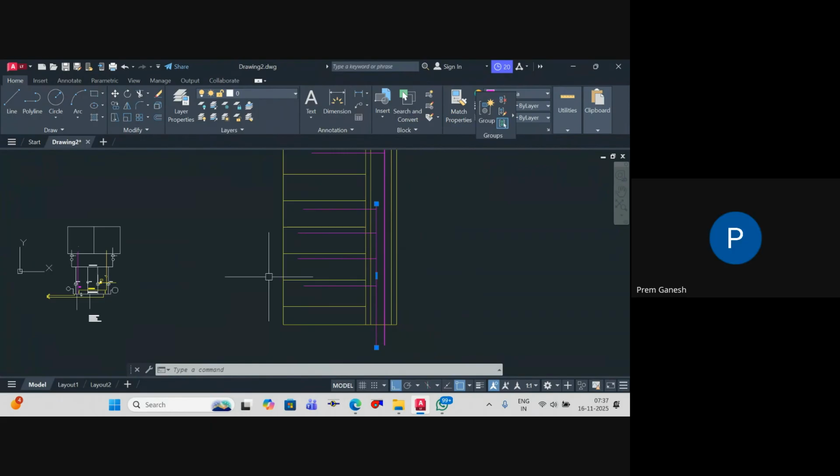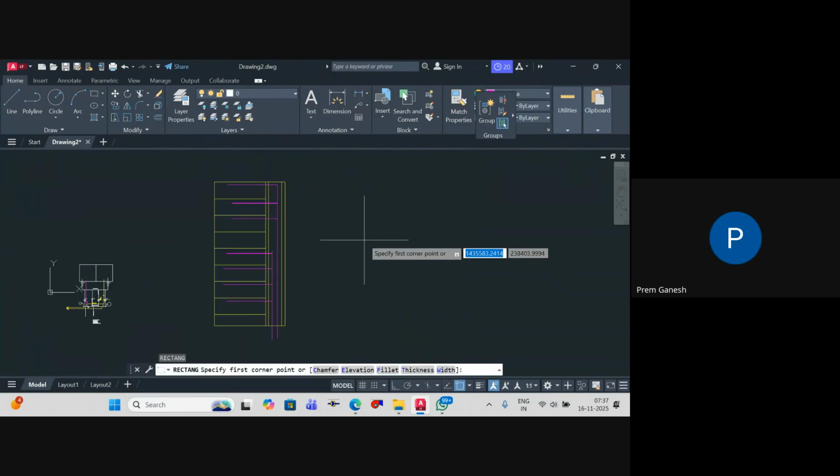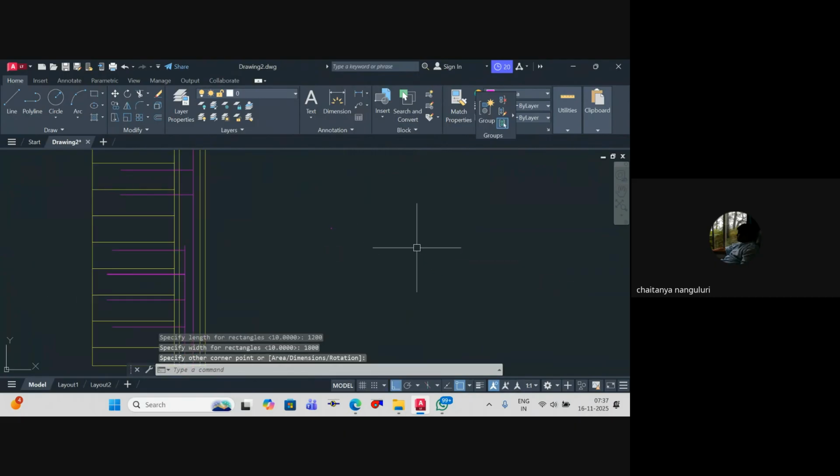And sir, one more thing in this FHA shaft, sir. Usually, what will be the piping arrangements? Means the size of the shaft. Okay, that is around 1.2 meters by 1.8 meters is comfortable. 1200 by 1800, if you have it, that will be comfortable for you.